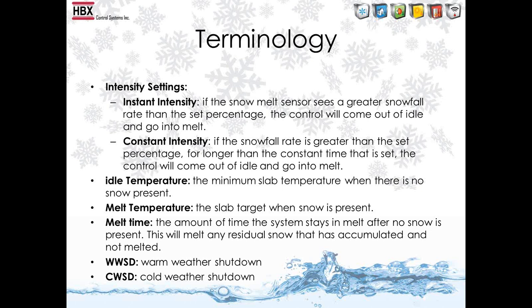Cold weather shutdown depends on how the system has been designed. So if the system's been designed only to produce enough BTUs at, let's say, a minus 10 degree outdoor temperature, then it doesn't matter how many BTUs you try to put into it, the system will not warm up the slab below minus 10. So you would set your cold weather shutdown at that minus 10, because you don't want it to work down there, since it's never going to melt the snow anyway. It will continue to run and run and run and waste a lot of money.